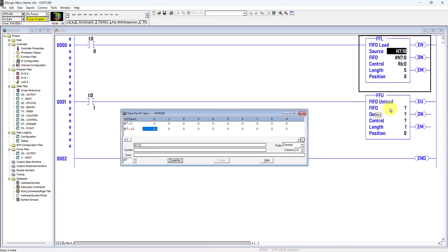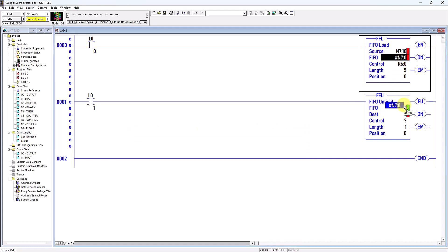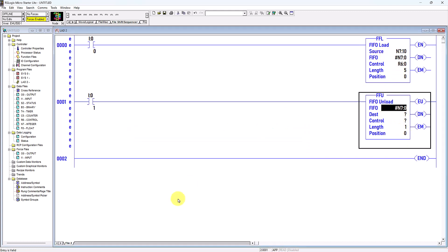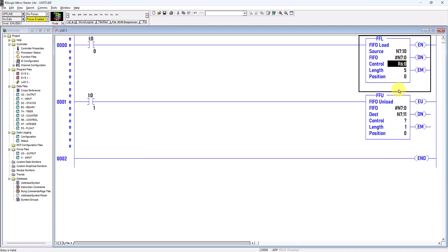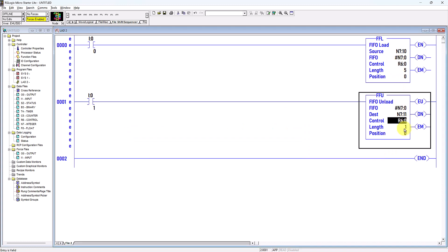For the FFU I will use the same file address as the FFL, so I copy that here. For the destination I will use N7:11, dragging to here. This is my destination. For the control I use the same control word address, and I use 5 for my length.